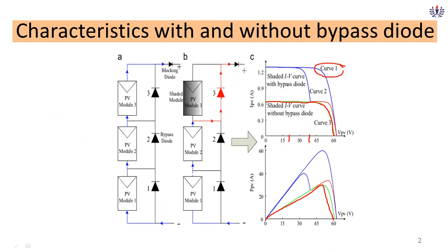During that time there will be a reverse voltage, because the PV module cannot deliver 10 ampere; it has only the ability to produce 5 ampere. So in that case the maximum voltage is going to be 40 volt. Why? Because one module is getting bypassed. So when the load demands 10 ampere, the maximum voltage deliverable to the load is 40 volt, but again the current value can be improved.